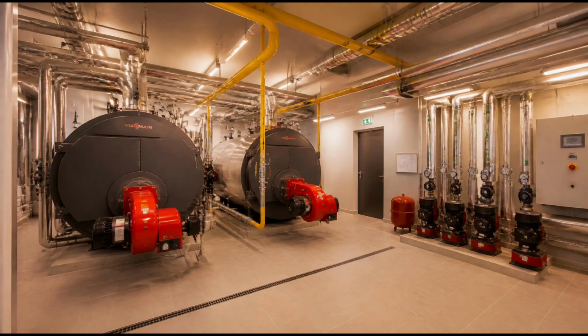Building automation systems are also programmed with schedules. They know when the building is typically occupied and when it is not. They anticipate the morning warm-up period before people arrive, bringing the building to a comfortable temperature before the first employees enter. They begin a gradual setback in the evening, easing the building's mechanical systems into a quieter mode as occupancy decreases. Zoned systems help different areas stay comfortable in different ways.